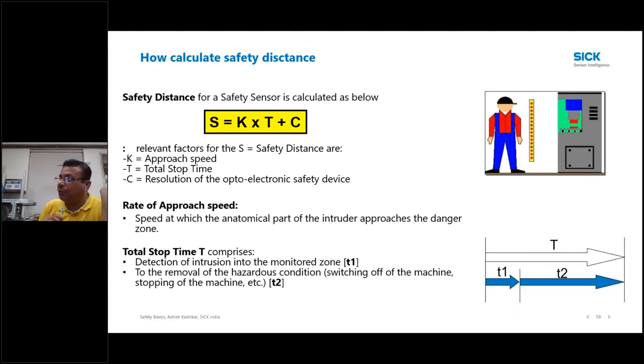The output of the safety product goes to a relay or contactor, from there to the PLC, and from the PLC to the motor. If you open the manual of all these products, you will find the response time, and you can do a mathematical calculation to get a total T. But after 2, 4 or 5 years, due to wear and tear, the response time of the machine may not be the same as explained in the manual.